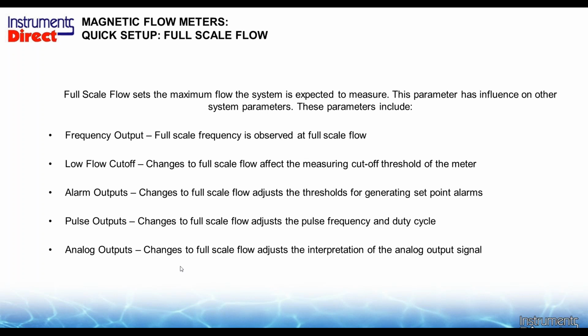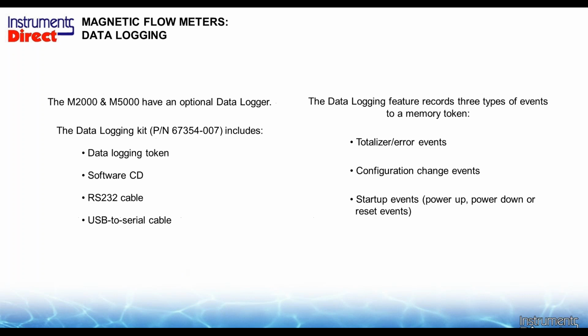to match your recorder chart paper if you wanted to, or any other device that you have in your facility, should you want to. This particular device has an option. You can upgrade it with a logger. And the device, especially in the battery-powered side, as we said before, if you don't have any power and you need to collect some data, there might be another method to collect data, using a data logger. The dedicated meter, of course, has a 4 to 20 milliamp output, so you could add a logger, or you could use the onboard logger.